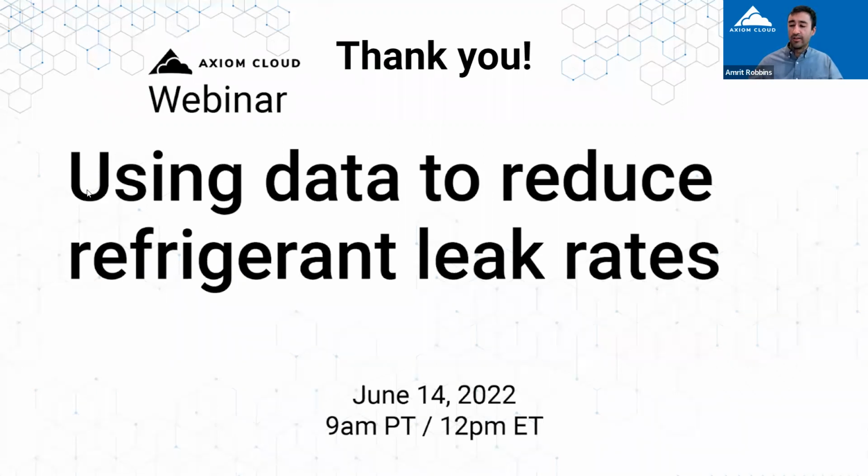The other thing that I want to add here is that even if you as an end user don't have all those sensors available today, there are still ways to enable this. Basically that involves using data analytics and modeling to create essentially virtual sensors. The idea here is you have all kinds of data around a specific sensor or where that should be, and you can use that to approximate what that sensor would be reading if it actually existed. That's again where data can become really powerful, helping to make these sensors appear out of thin air, even if you don't already have them, if you have surrounding sensors that are providing other relevant data streams nearby.